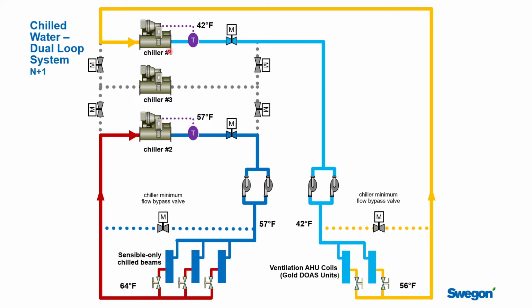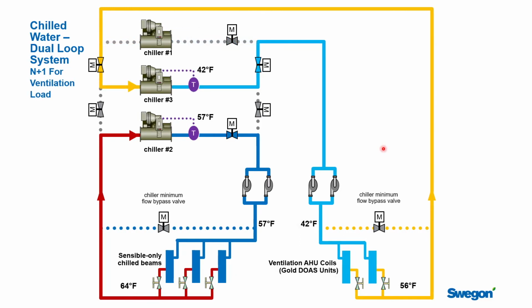We have another chiller up here that is pumping water up out to the air handling units, and it's running at 42 degrees to do the air handling units. So the loops have been separated, and we allow part of the chiller plant to operate at a more efficient point. So now one of the things we could do is, what happens if we have an issue with this chiller? Well, we could have a crossover chiller, this one that was available to us, and in fact if we needed both chillers to do that, we could operate both chillers to service this load, and through the valving we can allow this chiller to go and service the ventilation units and make 42-degree water to do that.